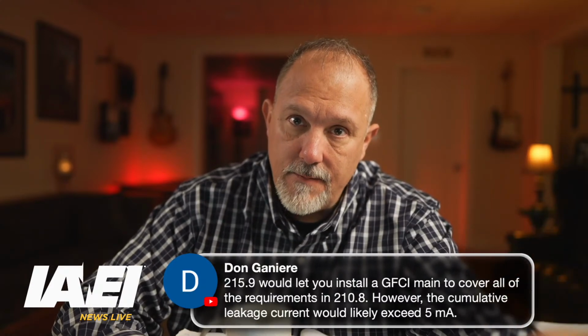Because what does OSHA tell us? OSHA tells us we cannot energize the circuit until we've cleared the problem. And if I have GFCI or GFPE up there at the service and it trips, and the problem isn't right there in that equipment, now it's somewhere else in the power distribution system, and I just can't re-energize until I find the problem and isolate it. Because you could kill somebody. You could burn the house down. You could do a lot of different things that are ungood. Technical term, ungood. So in any case, there is a provision in 215.9 that would let us put GFCI further up in the system.